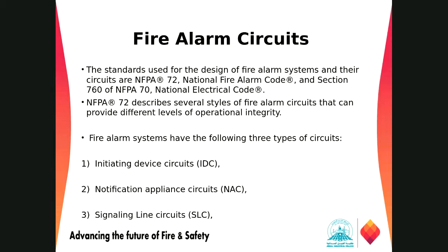So the IDC just connects fire alarm and supervisory devices, right? IDC will connect fire alarm and supervisory devices to the fire alarm control units. The second one we have is the NAC. It is connected to the notification system, like horns, bells, speakers, strobes, voice communication systems, and so on. The last one we have is the SLC system, which we call the signaling line circuit.